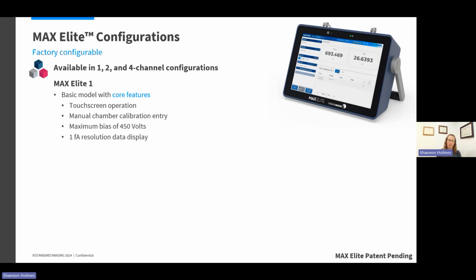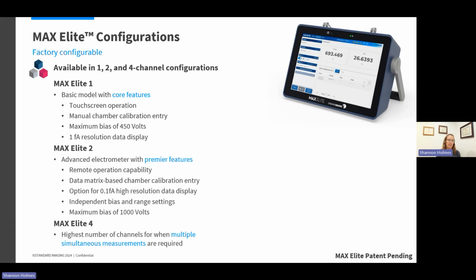The maximum bias voltage for the 1-channel version is 450 volts, which matches our Max 4000 Plus electrometer. And then the data resolution is 1 femtoamp, which is also matching our older electrometers. The MaxElite 2 and the MaxElite 4, the 2 and 4 channel versions, are the advanced electrometers that have that next level of premier features. So those are the ones that you can operate remotely. They are also the ones that have the camera for the data matrix based chamber calibration entry.